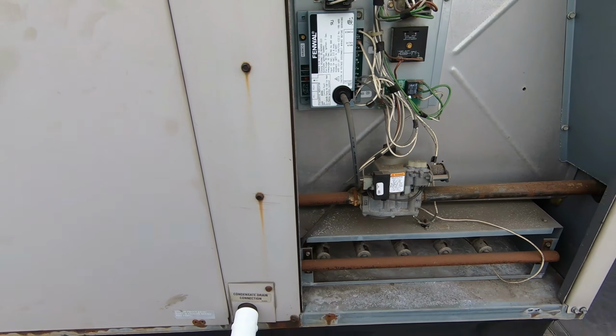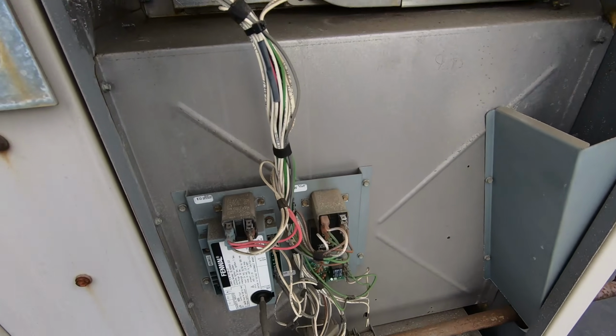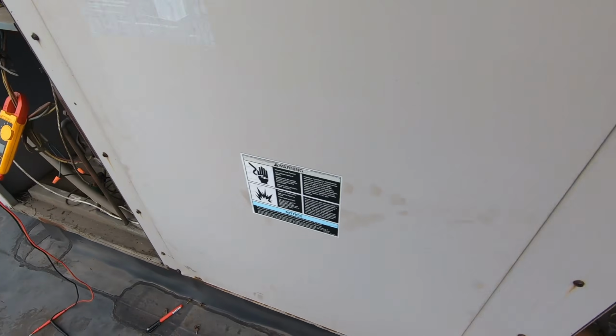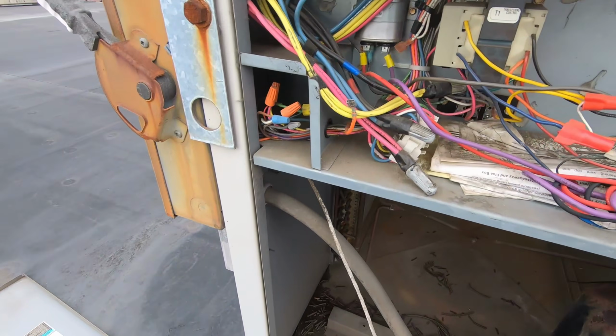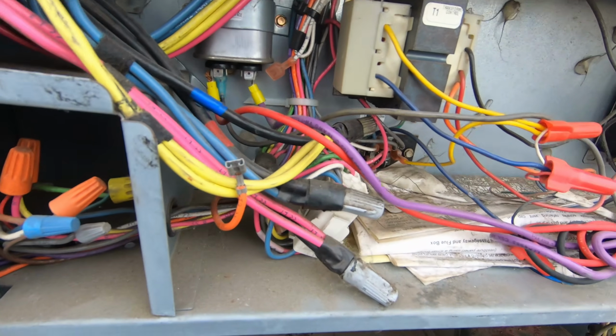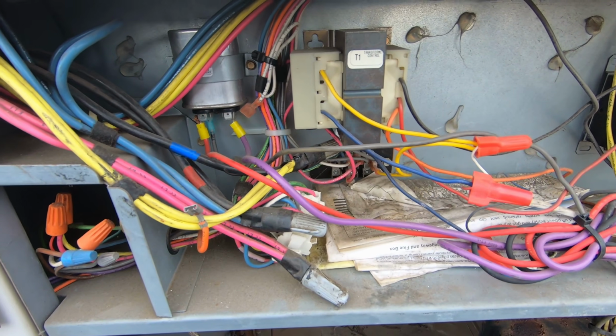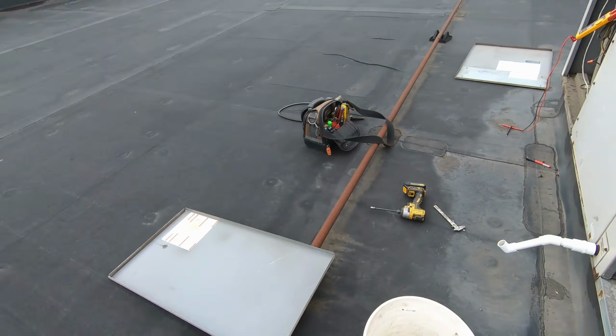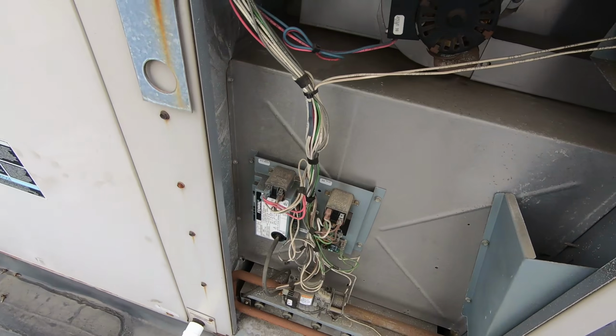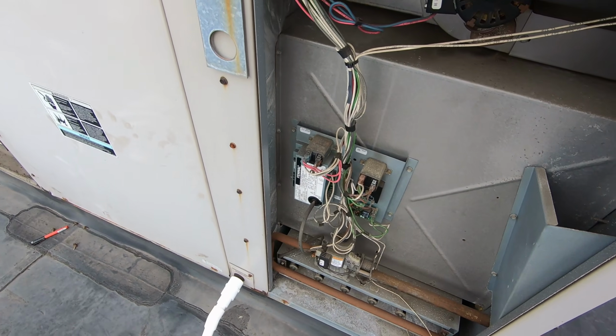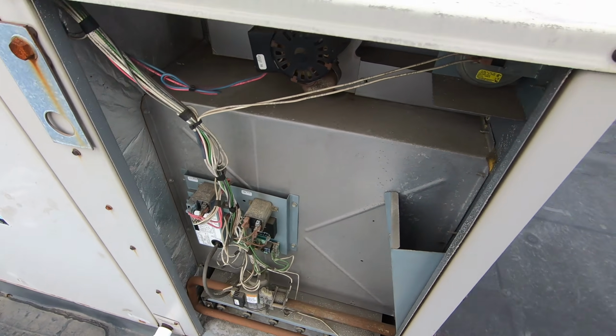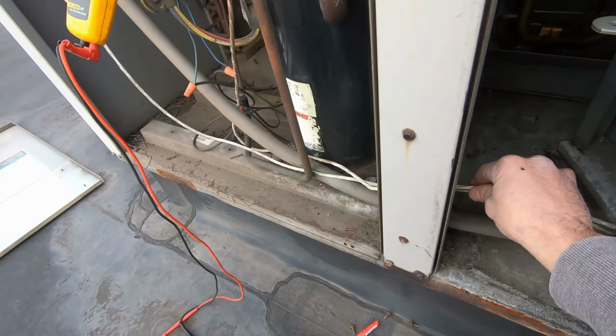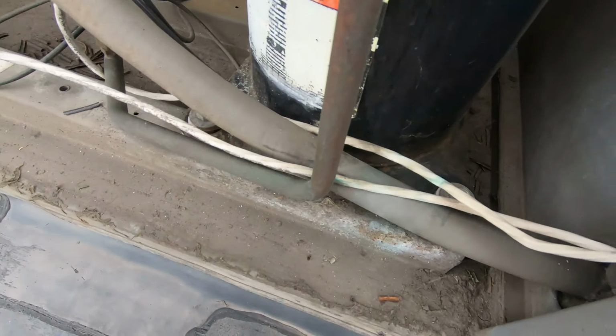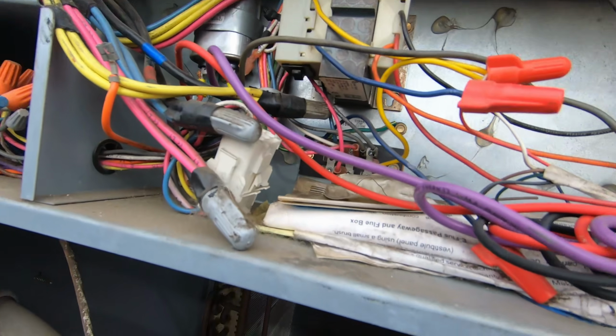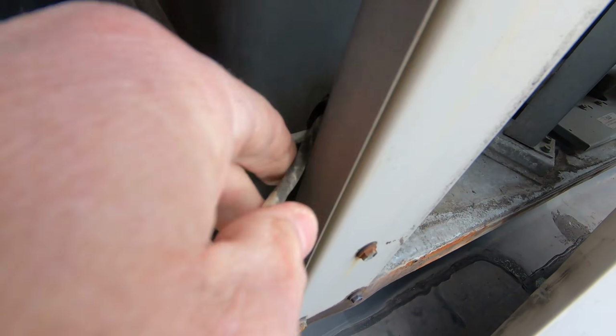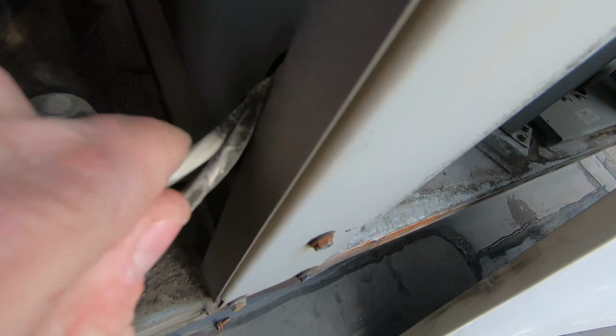All right, that's the problem with low volt shorts, guys. It takes a little bit of investigating to find, and now we're kicked on. We haven't had to reset our 3 amp breaker on the transformer. Definitely gonna need a combustion blower. So I'm gonna start compiling my list while I wait for this thing to trip again and see if we can't figure out what's causing it. Look at this, guys. Right there it is. Right there it is. It tripped it. No grommet. Oh, right there. See that?